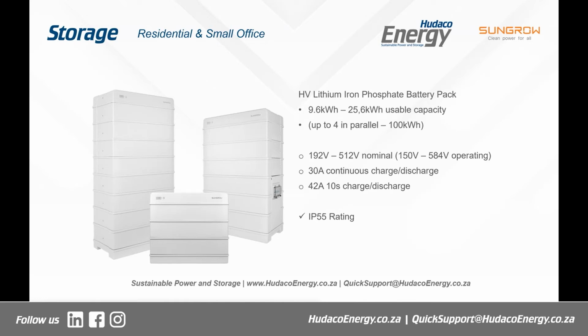And the commissioning process is so simple. On the top left of the BMS there, you'll see there's a little charge meter. Looks like a little battery with 10 little cells in it. And to the right of that is a little round circle. You hold your thumb over that for 3 seconds. The unit will fire up. It will auto commission with the inverter, and you are done. It's as simple as that. Again, an absolute game changer to make your life easy, make your clients happy. It looks good. It's easy to install.